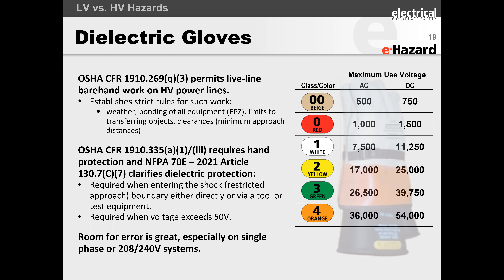And now I think this is the final that I have on the LV versus HV hazards: maintenance requirements. So at high voltage, gloves can only go up to 36 kV as per ASTM D120 and need to be maintained, electrically tested on a 6-monthly cycle, and obviously inspected before every use. Live line tools are dielectrically tested every 24 months. Bucket trucks, hoses, insulating blankets, etc. are all tested 12 monthly, right? So inspections are obviously mandated before every single use, whether you're high voltage or low voltage.